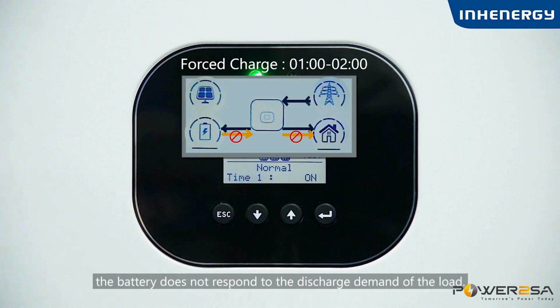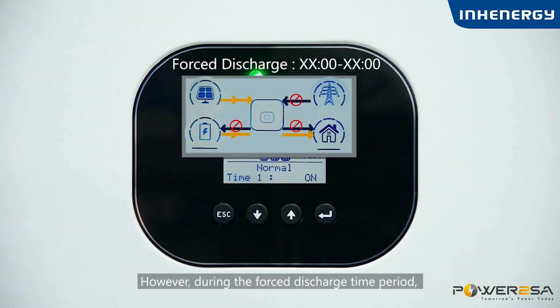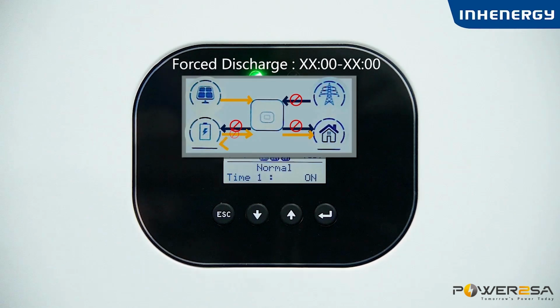During the forced charging time period, the battery does not respond to the discharge demand of the load. However, during the forced discharge time period, if the PV power is greater than the rated inverter power, the excess energy of the PV automatically charges the battery.